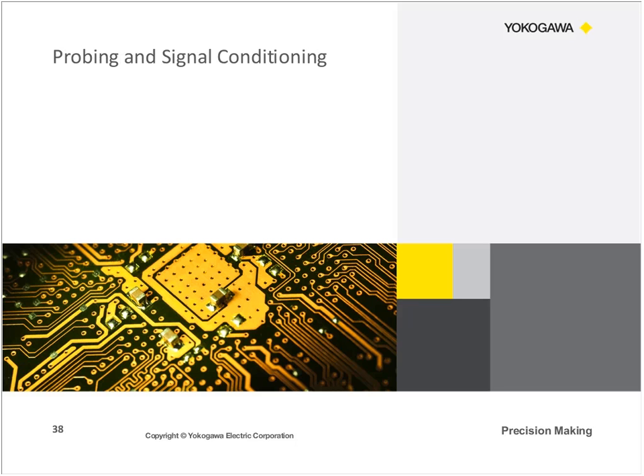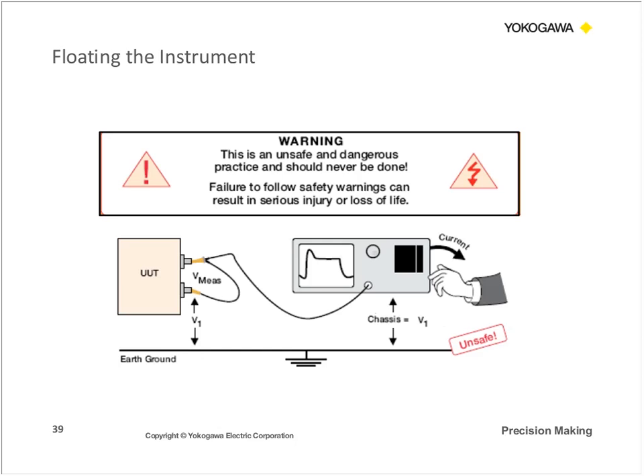So with all these isolation amplifiers, analog and digital, the next thing we want to talk about is probing and signal conditioning when we're connecting our data acquisition device to the instrument. Now, in the old days, one of the most unsafe practices that was introduced was floating the instrument. The idea behind this was that there was a need to measure floating signals, and at that time, differential probes were expensive.